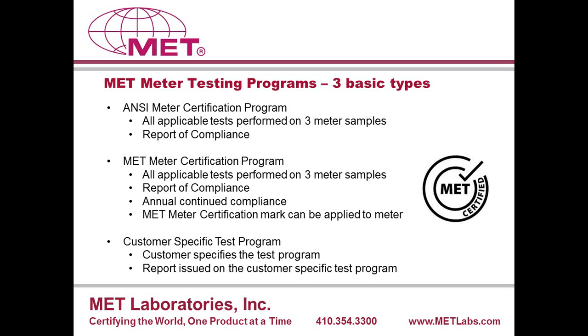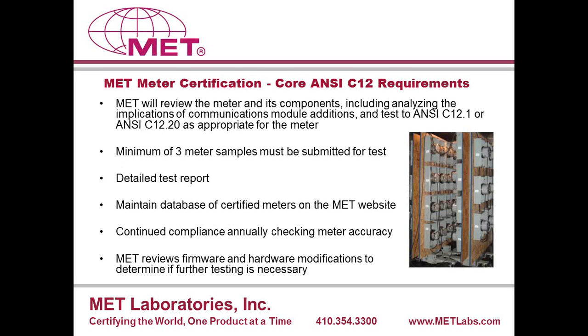And our third type of program is simply a customer-specific test program. If you have a meter that has been changed, some folks have been in the business forever, and they know that this change is going to affect these couple of tests, 2, 3, 4 tests. We really just want a quick test program on X amount of samples to show compliance with these particular tests. That's fine. That's not a problem. We'll certainly do that for you as well. That's what our customer test program is about. Maybe you have a test program that goes beyond what's required by ANSI, that sort of thing. In that case, we'll run our testing, and upon completion of the successful test program, depending on your test pass-fail criteria, a report of compliance is then issued. So that's the 3 basic test programs we have here for our metering.